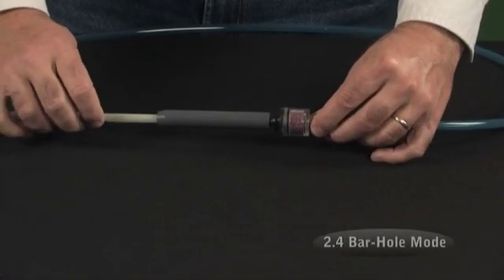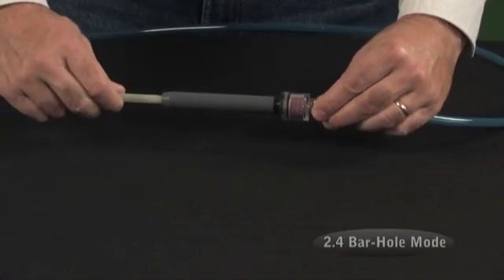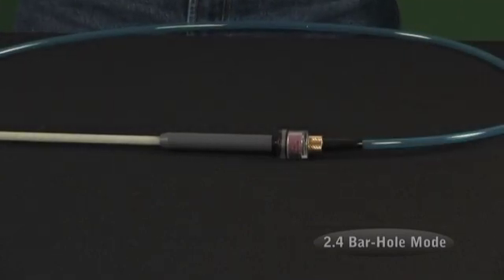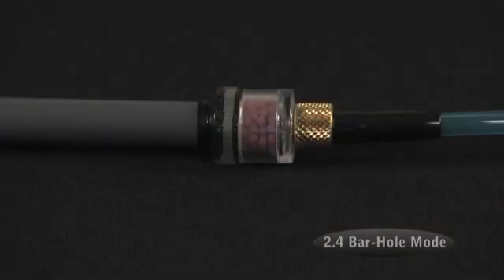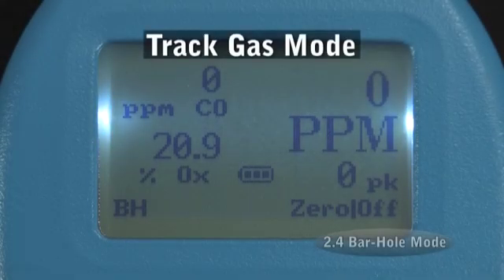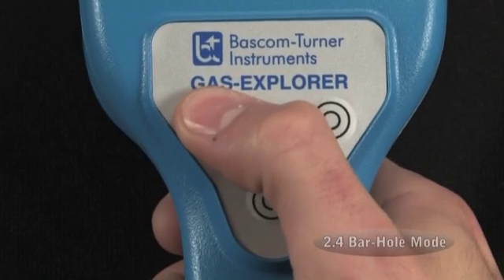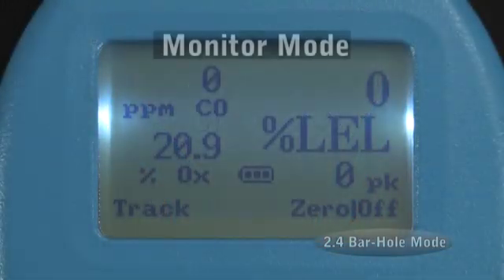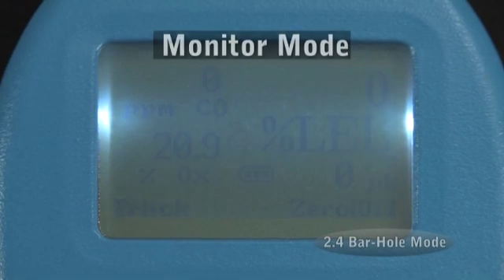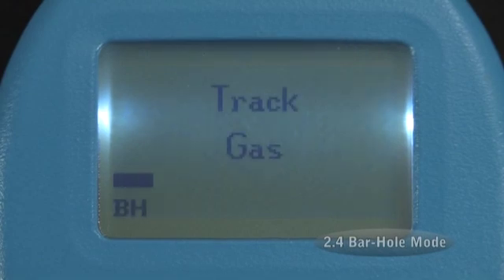To bar hole, connect your bar hole probe and any supplemental filters to the detector, making sure that the primary filter is in place between the probe and the detector. You can enter the bar hole mode in two ways. From the track gas mode, press the left button marked BH. Or from the monitor mode, press the left-hand button marked Track, and then, when track gas appears on the display, press the left button again, which is now marked BH.